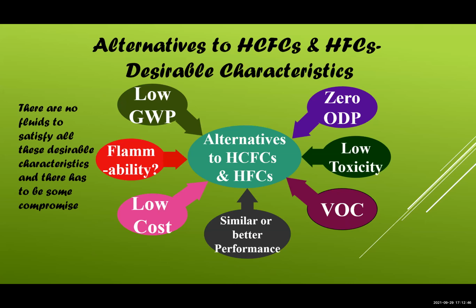So you have a real technical challenge: you have to choose a fluid which is low GWP and affordable cost, but it has to still perform. Like Omar said, most of the new refrigerants are better. Of course, you can make a refrigerant as good as possible through design changes, but then cost is a factor. One of the TEAP reports said that it doesn't matter what refrigerant you use, you can match the existing system through various technological options, which is true.